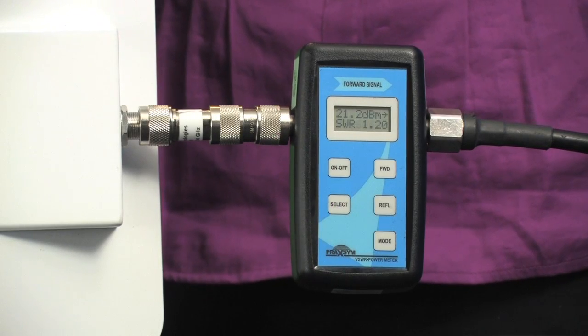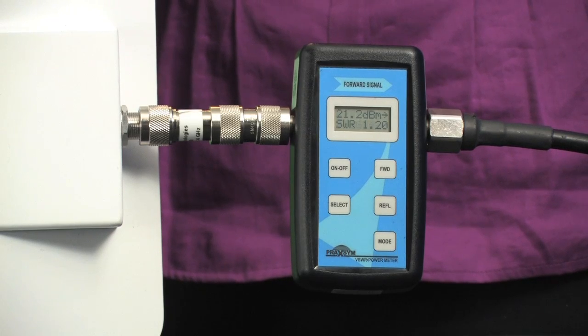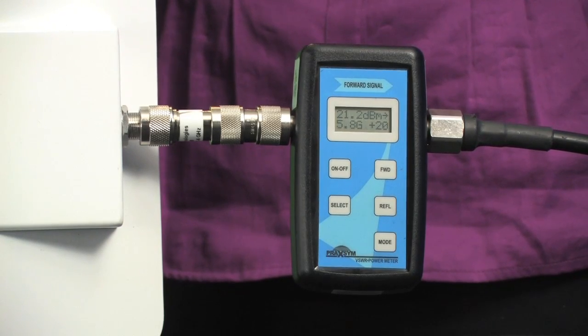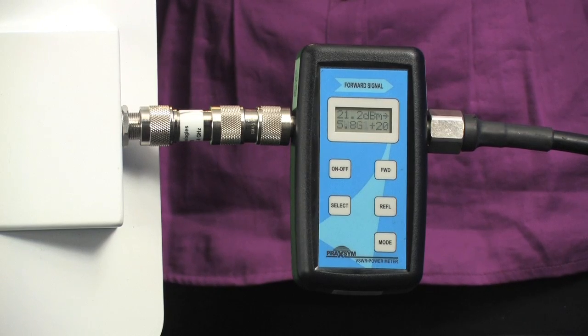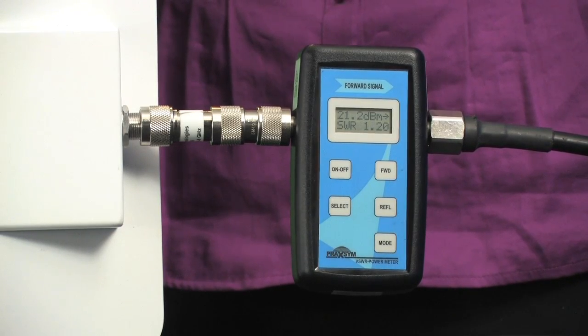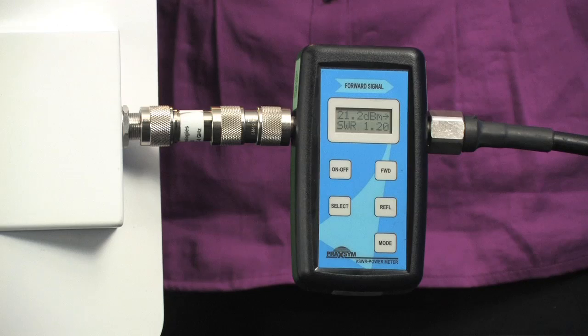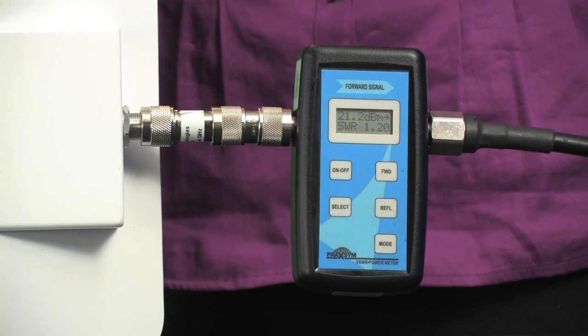One of the most common failures in broadband wireless systems is due to poor transmission line terminations. A lot of things can go wrong with terminations in the microwave frequency bands. The higher the frequency, the more likely termination issues become. With the T-meter installed between the radio and the first coax connector, a VSWR measurement will indicate the performance of that nearest termination. The T-meter might also be able to identify problems with the transmission line in the first several feet beyond the first termination.